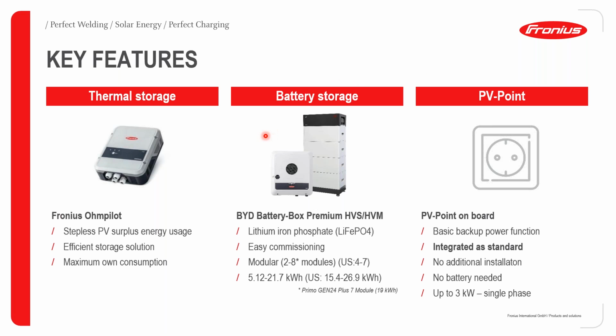The next compatibility aspect or feature is with a battery system. And as I have already mentioned, we now have the possibility with the Gen 24 Plus to connect a lithium iron phosphate battery. This is where you need to be a bit careful with connection, or when you are specifying battery storage for Gen 24 Plus inverters. We have a compatibility list on our website, and if you require, it can also be sent to you, so that you know exactly which batteries can be used with which version of the Gen 24 Plus inverters. At the moment, the battery that we recommend mostly is the BYD Battery-Box HVS or HVM. And these batteries can also be connected modularly to meet your power requirements.